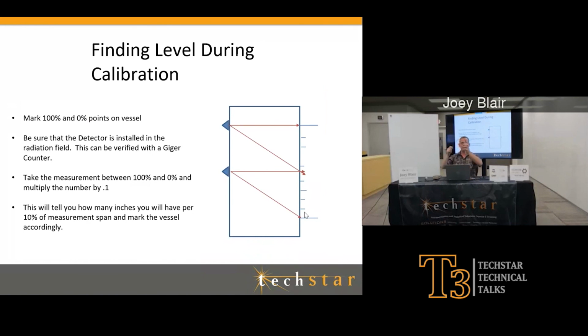If you're not filling, you can lower it instead. If you're up high, you'll read high radiation, and when you get to the point where the process is, suddenly you'll see your needle drop. You put a mark on the vessel to make sure it's not an obstruction I'm seeing. Sometimes I ask operations to move that level a little bit and make sure that point changes, which helps me find level during calibration, or just as extra verification if you want to confirm your level's right.